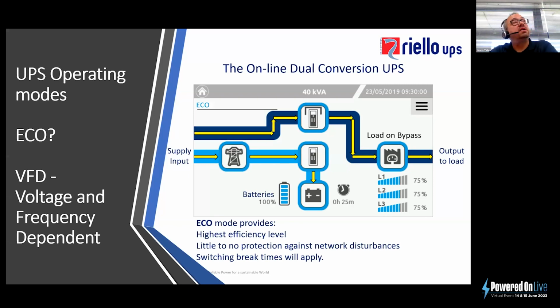In addition to this, in most systems, in the event of a main supply failure, there would be a small break in the supply to the critical load. We're only talking milliseconds when the main supply break occurs, and therefore, obviously, this is not a favored mode of operation by data center managers.